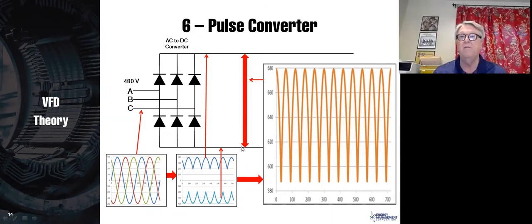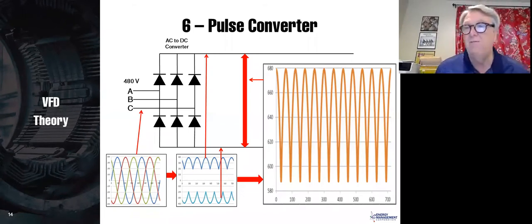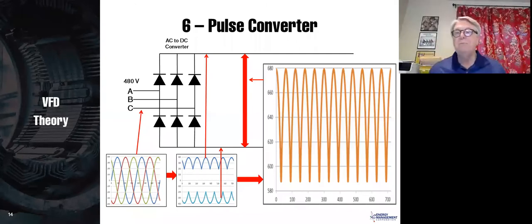Now, if we measure the voltage between the negative bus and the positive bus, it looks like this here that I have blown up. You'll notice that when I blew it up, I changed the scaling. So it starts at 580 volts. So the bottom of that waveform is about 587 volts, and the top of the waveform about 680 volts. So we have rectified AC to DC.